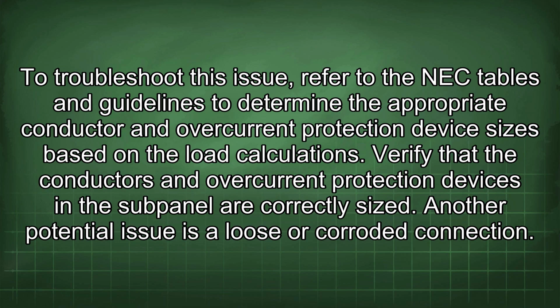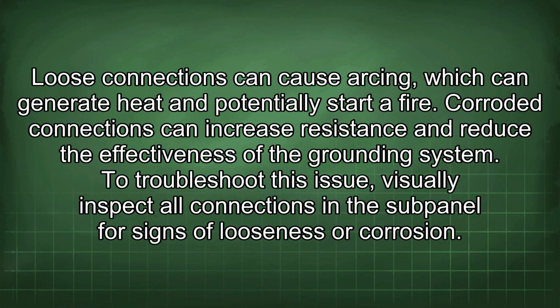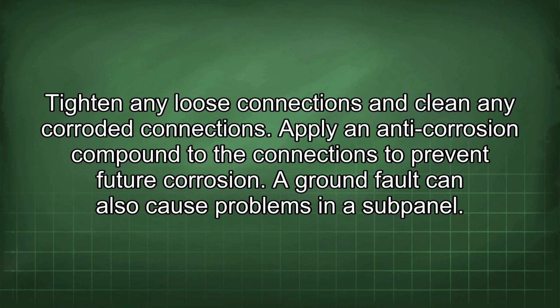Another potential issue is a loose or corroded connection. Loose connections can cause arcing, which can generate heat and potentially start a fire. Corroded connections can increase resistance and reduce the effectiveness of the grounding system. To troubleshoot this issue, visually inspect all connections in the subpanel for signs of looseness or corrosion. Tighten any loose connections and clean any corroded connections. Apply an anti-corrosion compound to the connections to prevent future corrosion.